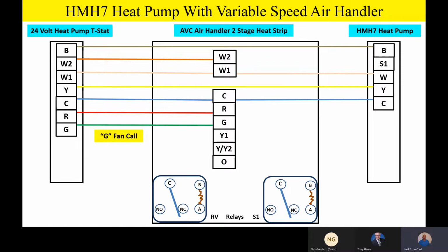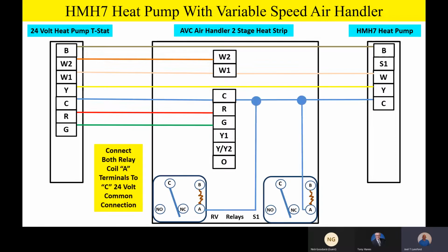G is our 24-volt fan call. That's what you'd expect, and typically a green wire is used, very common in the industry for our fan call. Now, as we take a look at those two relays, remember, this is the 002 kit. But if you had two peanut relays mounted in there, it would do the same thing as long as they've got 24-volt coils. So on those relay coils, take one side of each relay coil and take them both up to common and tie them together.